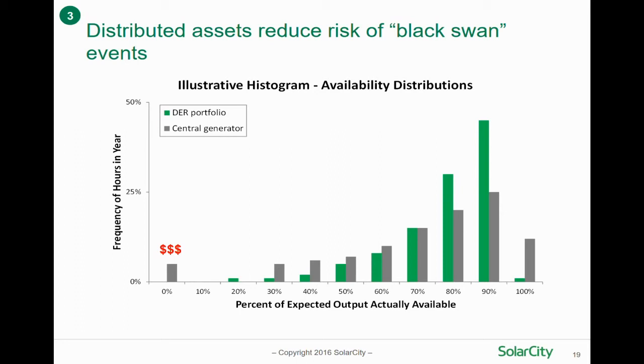Conversely, with smaller distributed assets, your N-1 scenario is maybe the battery in my home fails - no one needs to plan for that. That's maybe not a realistic scenario, but there are other batteries on circuits, call them 10, 15, 20 megawatt batteries. Some that Southern California Edison are putting in now are on the order of 40 and 100 megawatts. Those are still much smaller than the traditional scale on the grid.